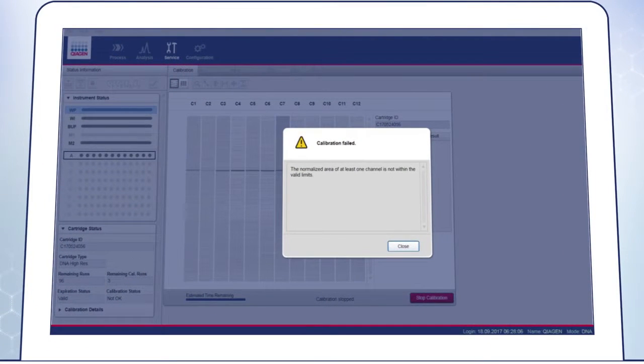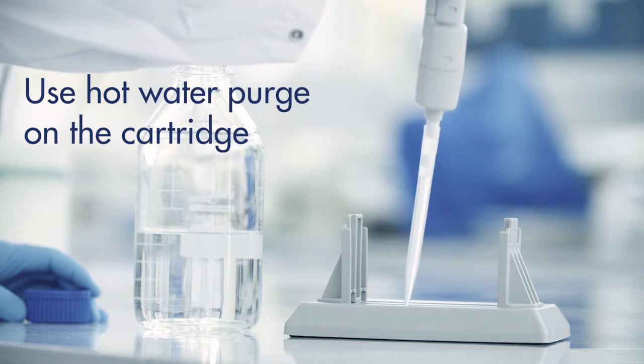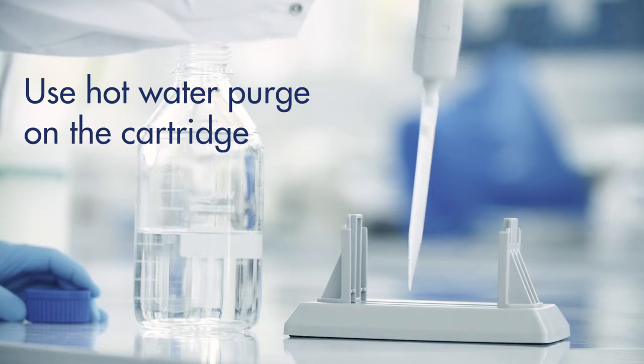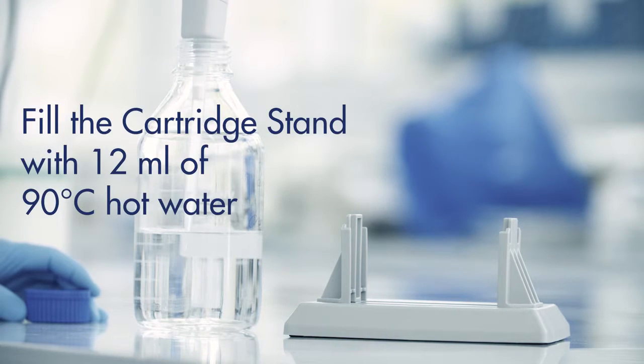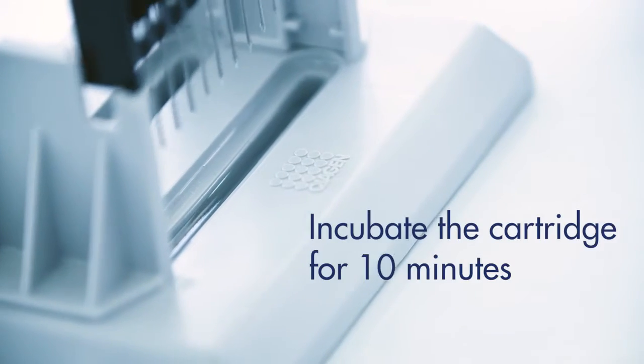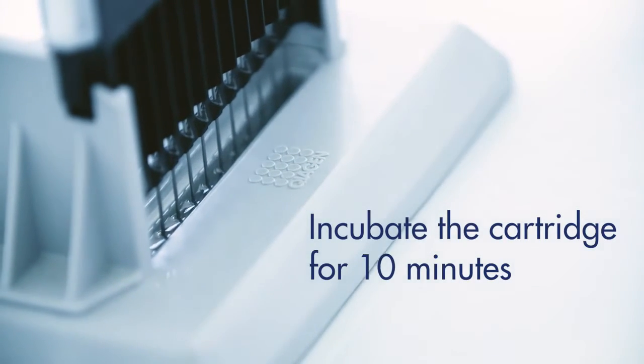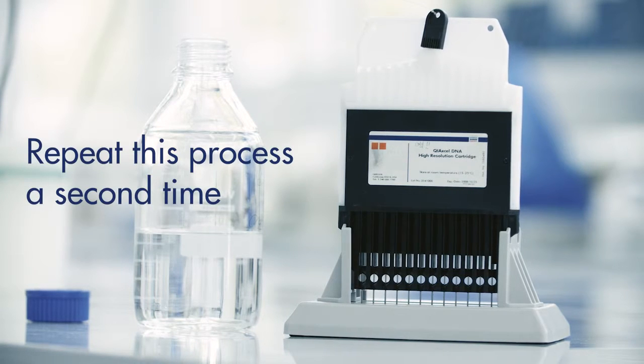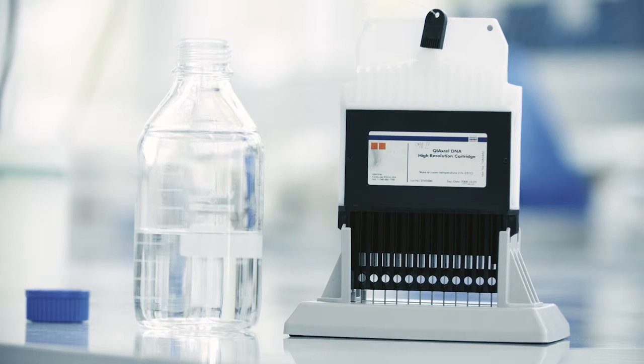If the calibration of the cartridge fails, or if one or more positions show high background, or in case you see ghost bands, this is usually due to dried gel which blocks the capillaries. In such cases, we recommend performing a hot water purge on the cartridge. To do so, first fill the cartridge stand with 12 milliliters of 90 degrees centigrade hot water and incubate the cartridge for 10 minutes. Repeat this process a second time after exchanging the hot water. This should soften the gel in the capillaries.